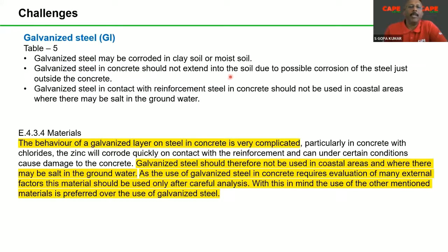Galvanized steel in concrete should not extend to soil due to possible corrosion from steel just outside the concrete. I have a picture I will show you. Galvanized steel in contact with reinforcement steel in concrete should not be used in coastal areas where there may be salt in groundwater. You see, one technique which is used is foundation earthing. In foundation earthing, the conductor is inside concrete and the concrete or the RCC floor is in soil. It is called wet concrete. A concrete or an RCC which is in soil is often called wet concrete. That means it has some wetness, and the resistivity of that concrete is approximately 100 ohm meter. That is what is specified in the standard based on several studies.